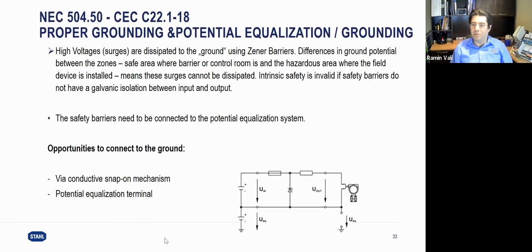The other code which is definitely important to be considered is 504.50 or Canadian Electrical Code C22.1-18, proper grounding. So according to the code, we have to have isolated grounding between the safe area and classified area. That's why we call our isolators an isolator. They are associated apparatus, but we call them isolators because of this transformer inside. Or if we are using a Zener barrier, we have to make sure that the potential between the ground in the field and the ground in the safe area is equivalent. Basically, we need a very low resistance type of grounding to connect it. And that's part of the protection method by Zener barrier, because we need to discharge the energy to the ground before extra energy is propagated to the field.